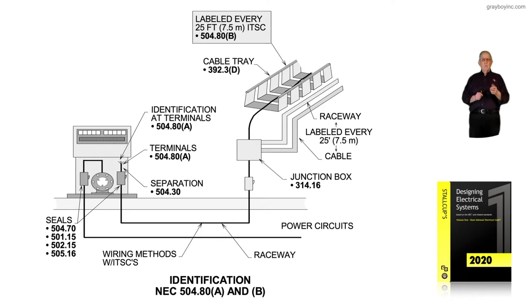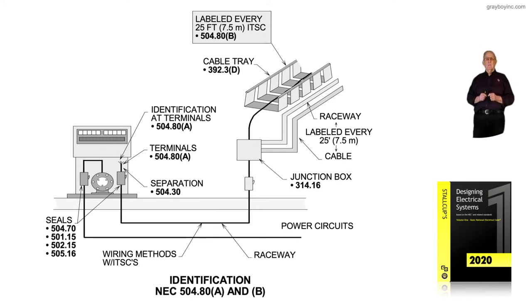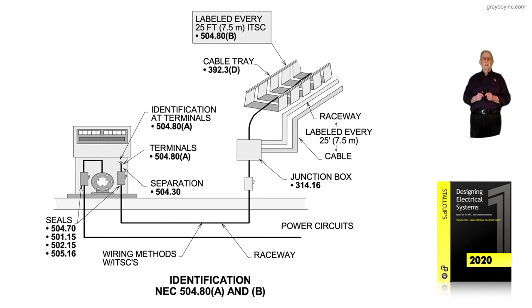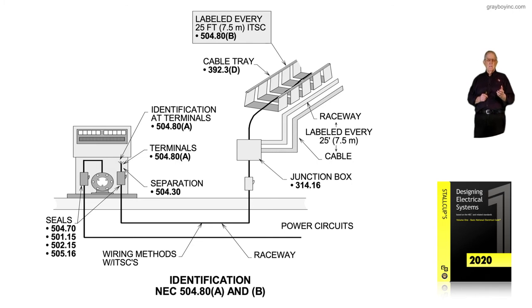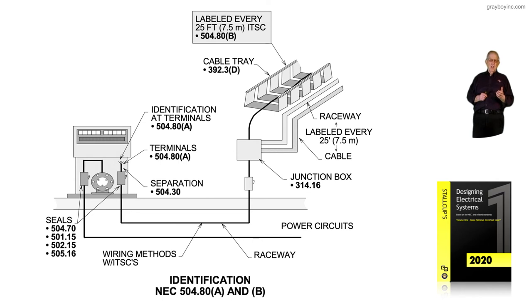The separation rule is in 504.30. You have the identification of the light blue coloring or labeling in 504.80. The seals required based upon certain conditions of installation are in 504.70 for intrinsically safe.